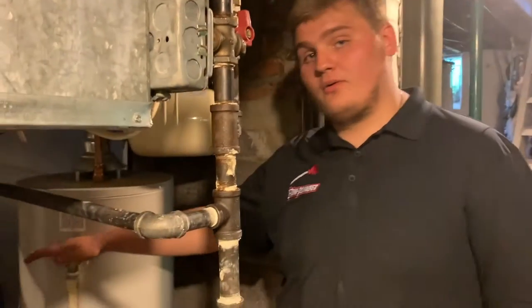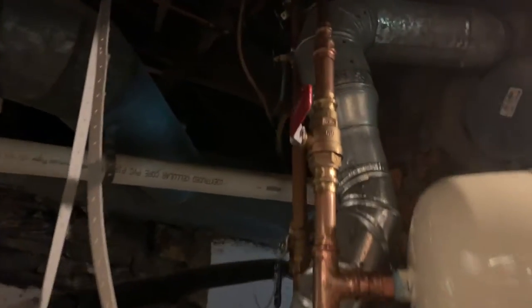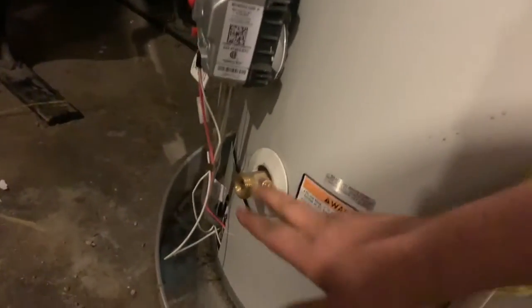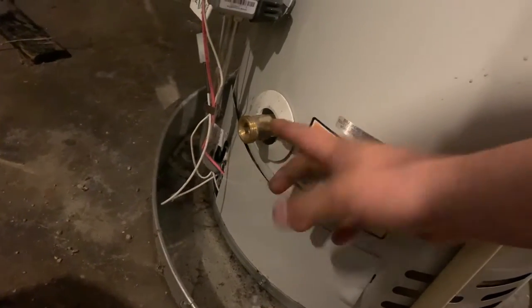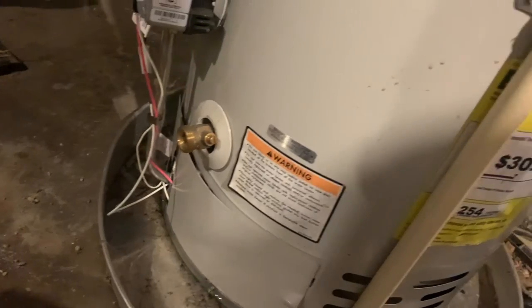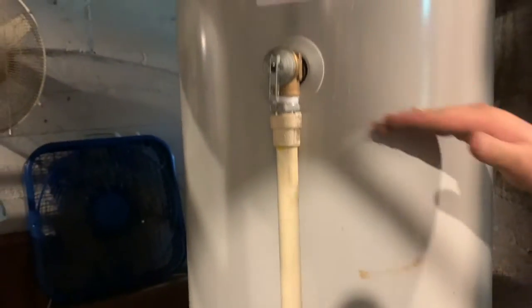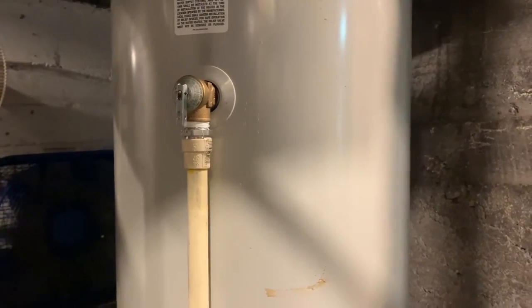All right, so in order to replace the T&P, what we'll need to do first is shut the water off and make sure that it's off. Usually, if you are a homeowner, I would recommend taking a garden hose and threading it onto this valve right here and opening up the valve to drain down the heater just to where the water level is below this, so you don't have any water splashing all over the place when you go to replace this valve.